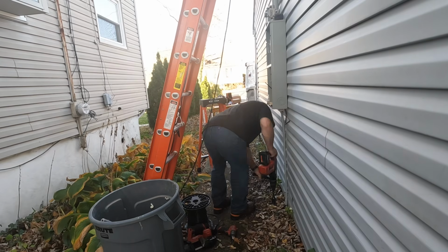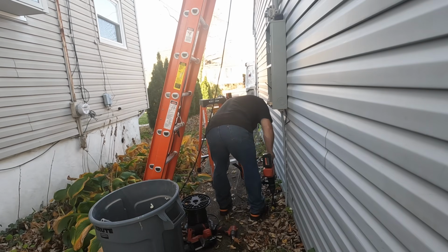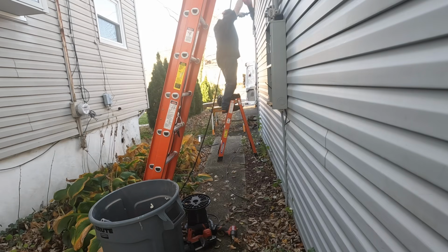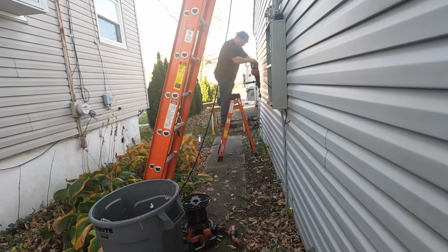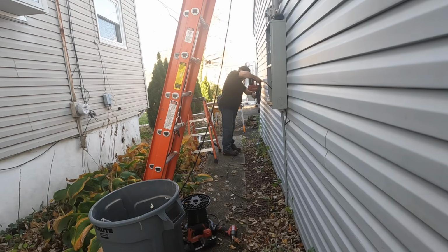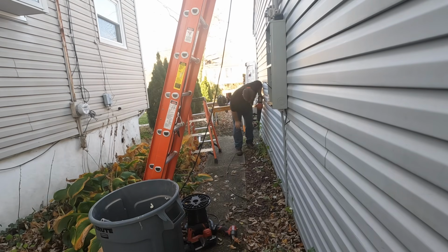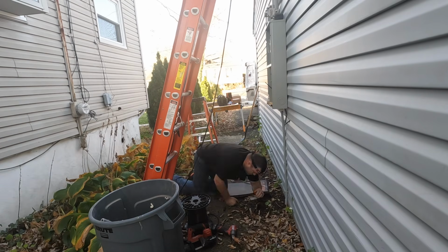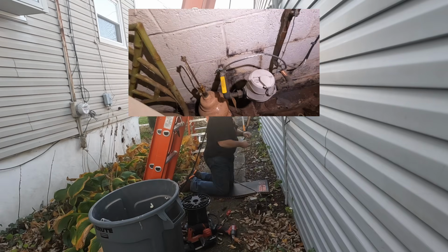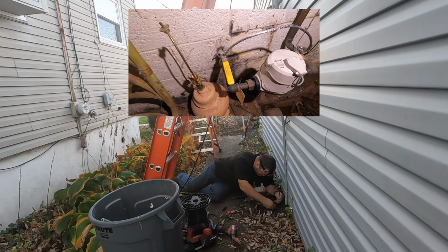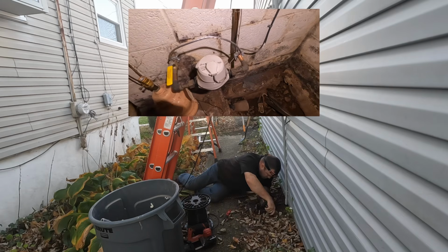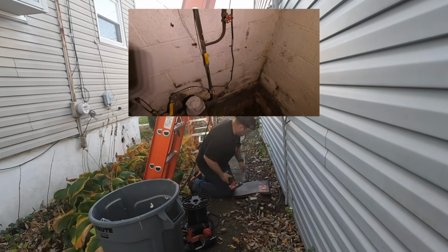We can never put aluminum in contact with the earth because it'll deteriorate. That's also in the code section, I think 250.64. Thank you, Ryan Jackson, for that. And number 6 copper is the largest conductor that you'll ever need for service when you're driving ground rods to supplement your other electrodes on the property. There's the water main in the picture-in-picture. Didn't get too much video of that, but I wanted to include it so you can see what it looks like when it gets done.